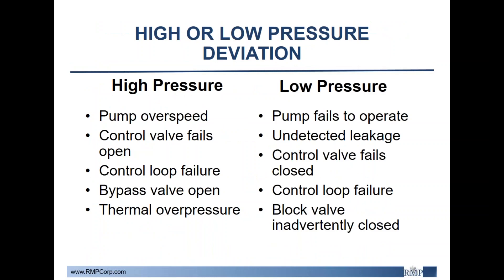Next is high or low pressure deviations. It's important to note that many of these causes were already discussed during the high and low flow deviations, so to avoid discrepancies, these causes should only be discussed in one deviation. If a cause was already discussed in a flow situation, it's acceptable to note no new causes. Common high pressure causes include pump over-speeding, control valves failing open, control loop failure, or thermal overpressure. Low pressure causes include pumps failing to operate, control valves failing closed, control loop failures, and a block valve inadvertently being closed.